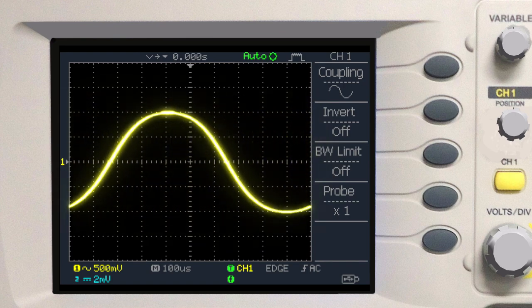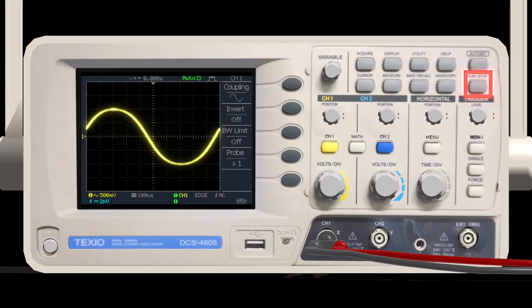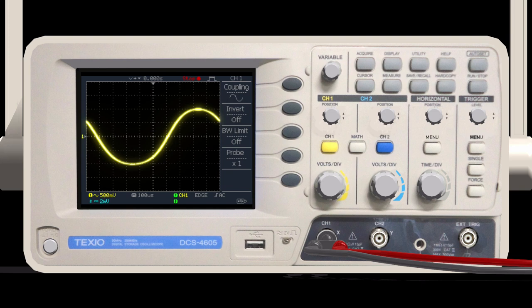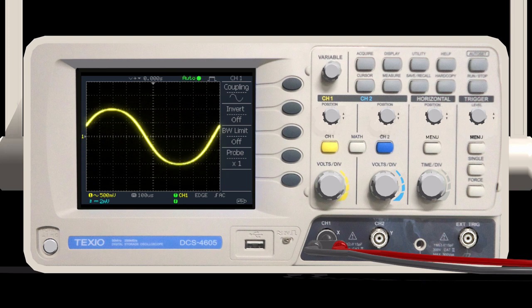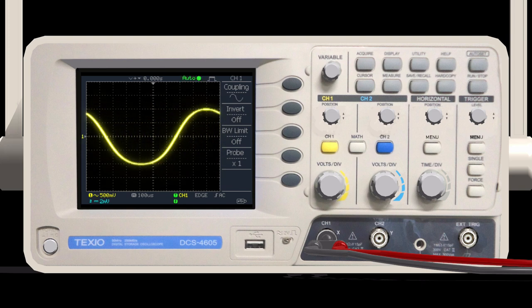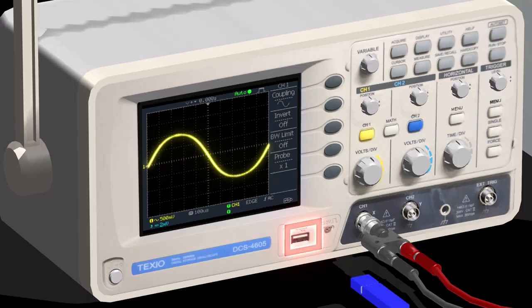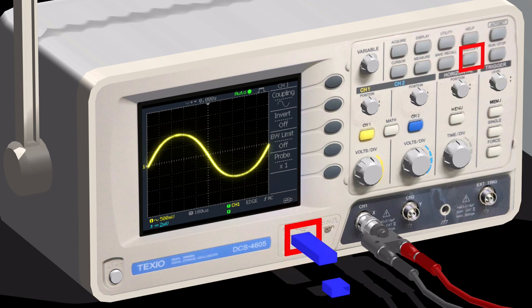If you want to stop the screen temporarily for observation, press the RUN STOP button. Press it again to start again. Insert a flash memory into the USB connector and press the HARD COPY button to save the waveform as an image.